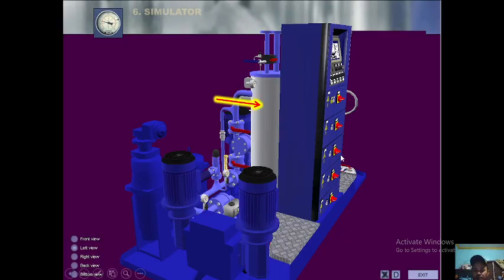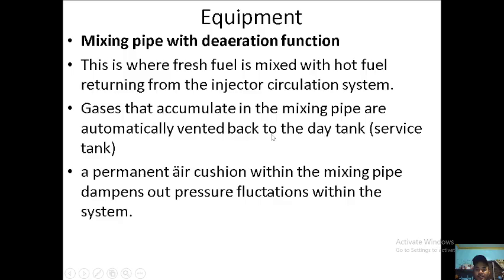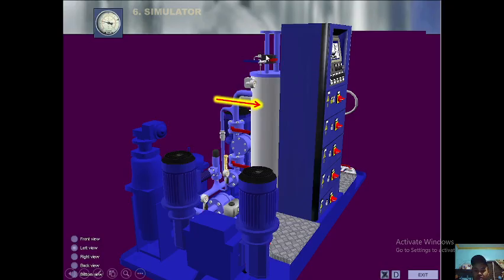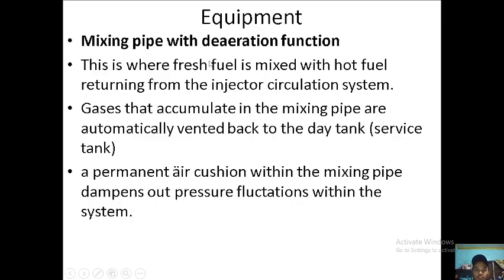Okay, at the back of our controller, we have the mixing tank, or the mixing pipe with the deaeration function. As you can see at the top, we have a deaerator. This is the one that will degas or deaerate the mixing tank if ever there are gases in this part of the FCM. This is where fresh fuel is mixed with hot fuel returning from the injector recirculation system. Gases that accumulate in the mixing pipe or the mixing tank are automatically vented back to the day tank. A permanent air cushion within the mixing pipe dampens out pressure fluctuations within the system to prevent damage to parts, valves, screws, and other installations.